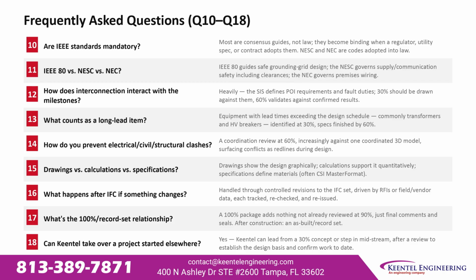How does the interconnection process interact with the milestones? The System Impact Study defines point of interconnection requirements and fault duties. The 30% one line should be drawn against those requirements, and the 60% package validates equipment selections against the confirmed study results. What counts as a long lead item? Equipment whose procurement lead time exceeds the design schedule, commonly power transformers and high voltage breakers. Identified at 30%, their specifications are completed at 60%, so procurement can begin before IFC.